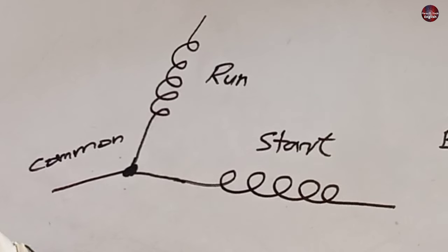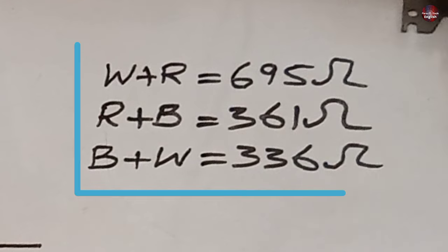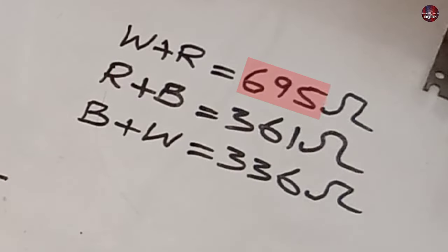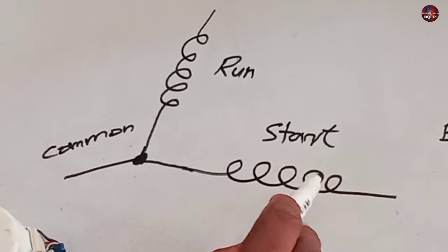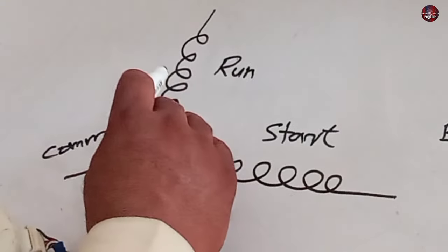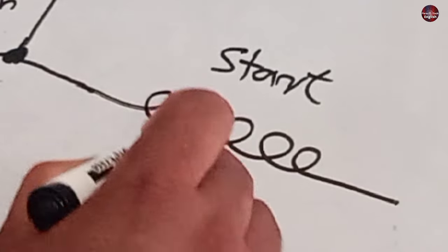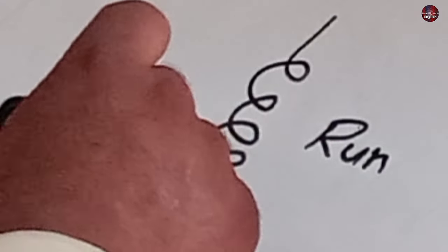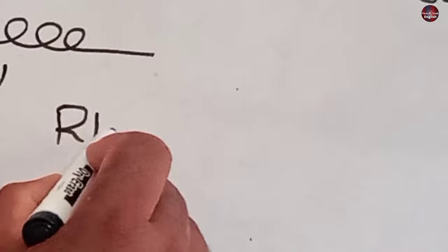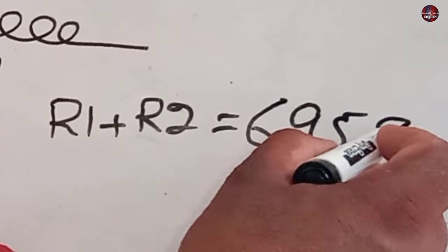Now I will tell you how to find the common, running, and starting through these values. The white and red wires gave a value of 695 ohms. This means the resistance of this winding and the resistance of this winding is showing us the values. I will name this start winding as R1 and the run winding as R2. Now I will add them both. R1 plus R2 is equal to 695 ohms.